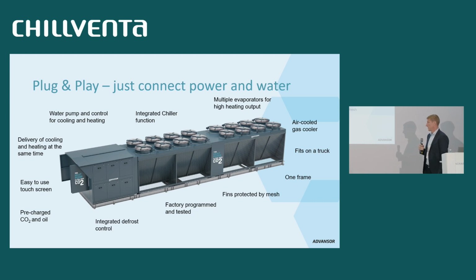If we look at the heat pump itself, then you see on the left side here, we have the machine part. And then on the right side, we have the evaporators or the energy collectors. So that's where we collect the energy from the ambient air to drive the heat pump. Everything is built together, one frame, fits on a standard truck. We have a mesh around the fins of the evaporator to protect it. But this also means that we can actually place the unit in a parking lot without setting up a fence around it, because it is protected and people are protected from getting hurt touching the fins.